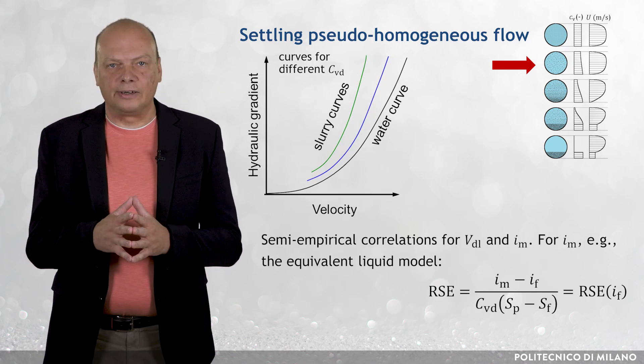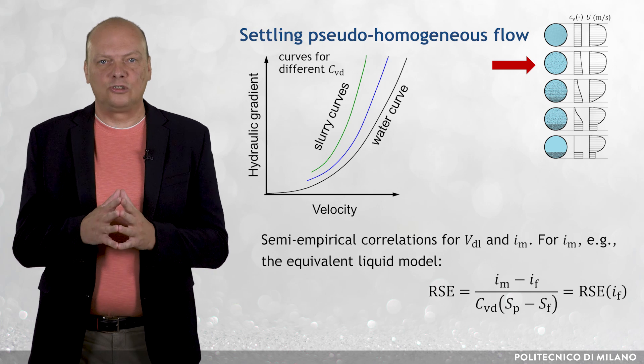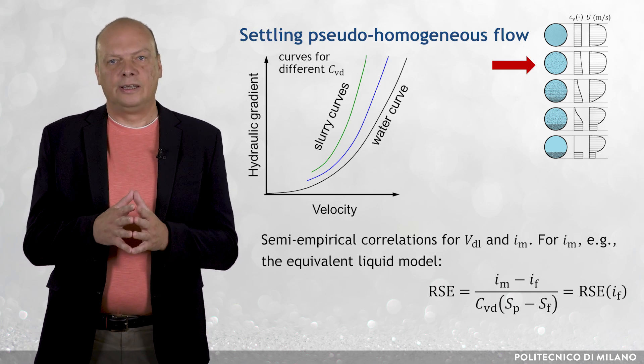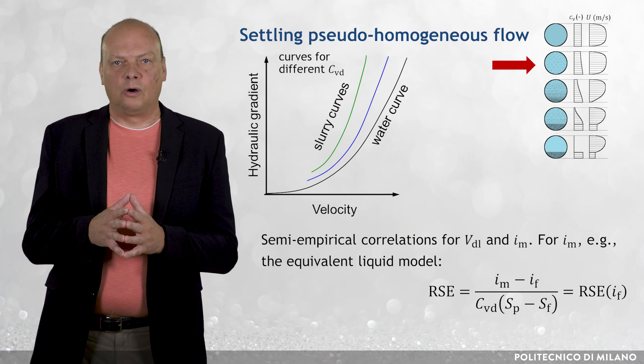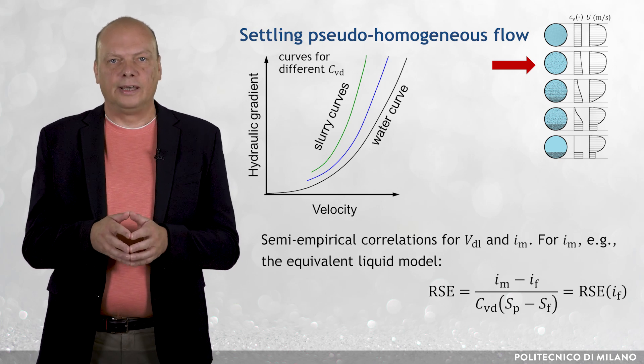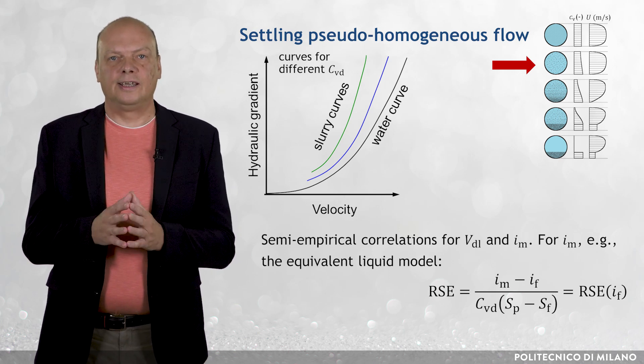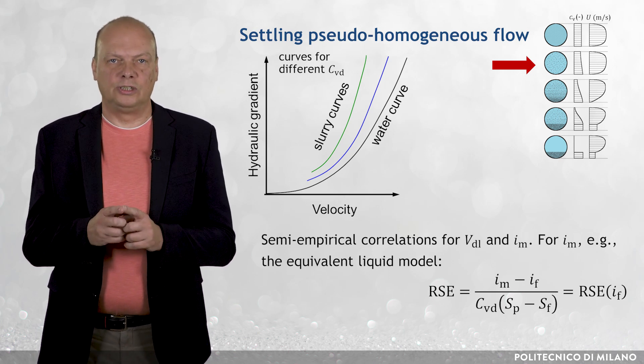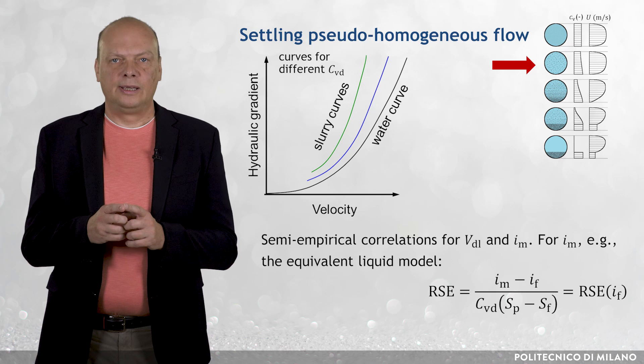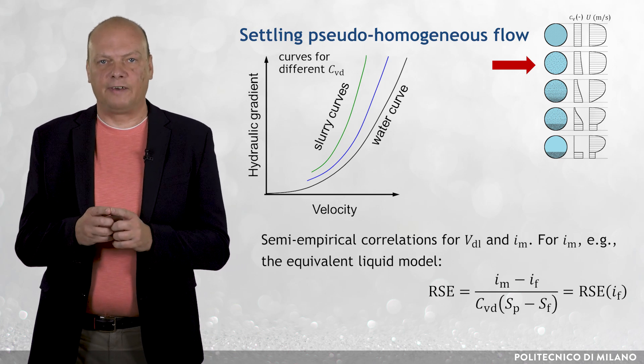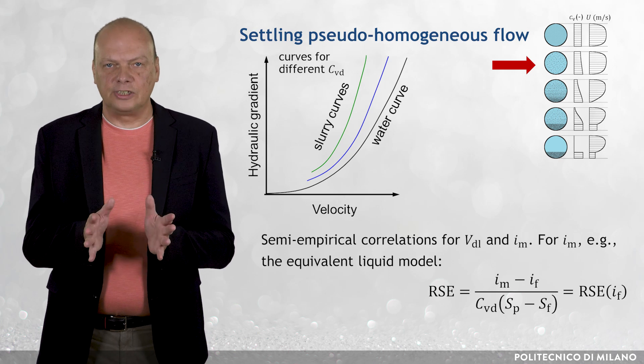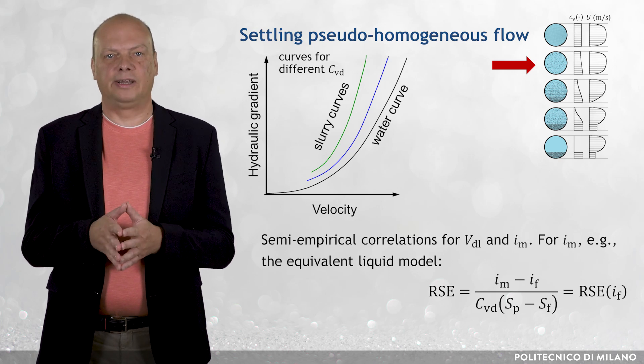Predictive modeling of the friction loss in pseudo-homogeneous Newtonian slurry exploits the concept of equivalent liquid. It simply assumes that at velocities of practical interest, the pseudo-homogeneous flow behaves as a single-phase liquid with the density of the slurry and the viscosity of the carrying liquid.